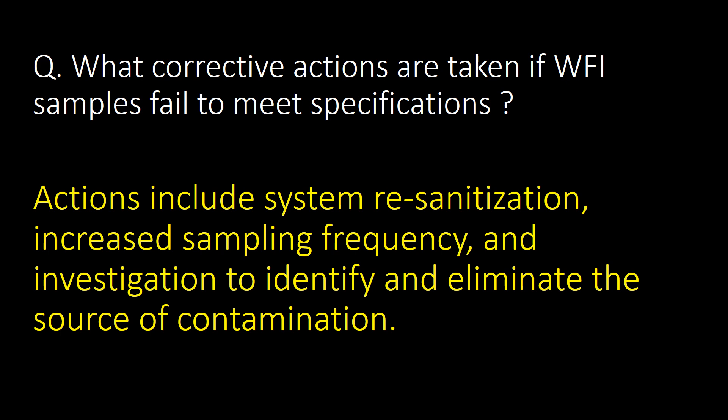An important question: what corrective actions shall be taken if WFI samples fail to meet specifications? Actions include system re-sanitization, increased sampling frequency, and investigation to identify and eliminate the source of contamination.